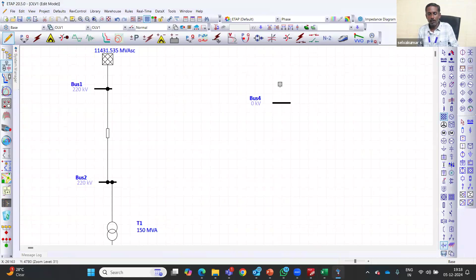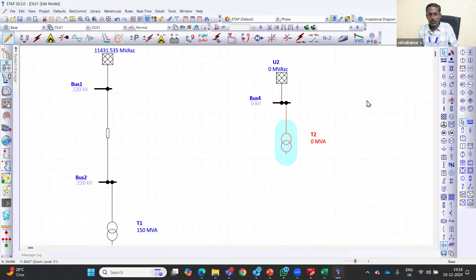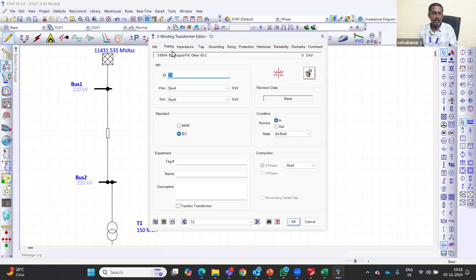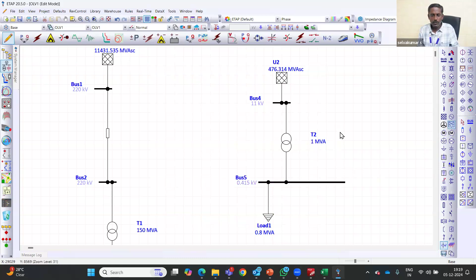So just to give a quick idea on the harmonics perspective, even if you're adding a small solar inverter as a part of your college campus, let's assume you're receiving power supply from 11 kV and you have, for example, a 1 MVA distribution transformer in your college campus, with some demand, for example 600, 800 kVA. And you're putting in a 500 kilowatt solar inverter. Let's do this analysis with and without solar inverters, then we will see the results and differences. I'm just putting up a solar inverter model.